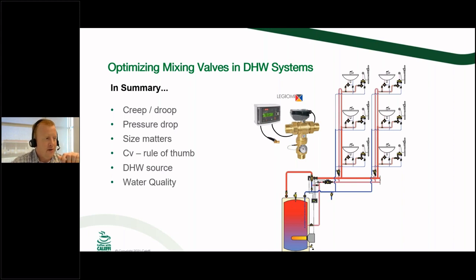I don't know if certain areas don't like it based on code, because obviously if you opened up that bypass, you could let full hot water, you know, 140-degree water out to the mixed outlet side. But for maintenance purposes, man, that bypass is a breeze. It's awesome. I mean, obviously you're going to take down your tank temperatures or your storage temperatures, so that way you're not going to hurt anybody.